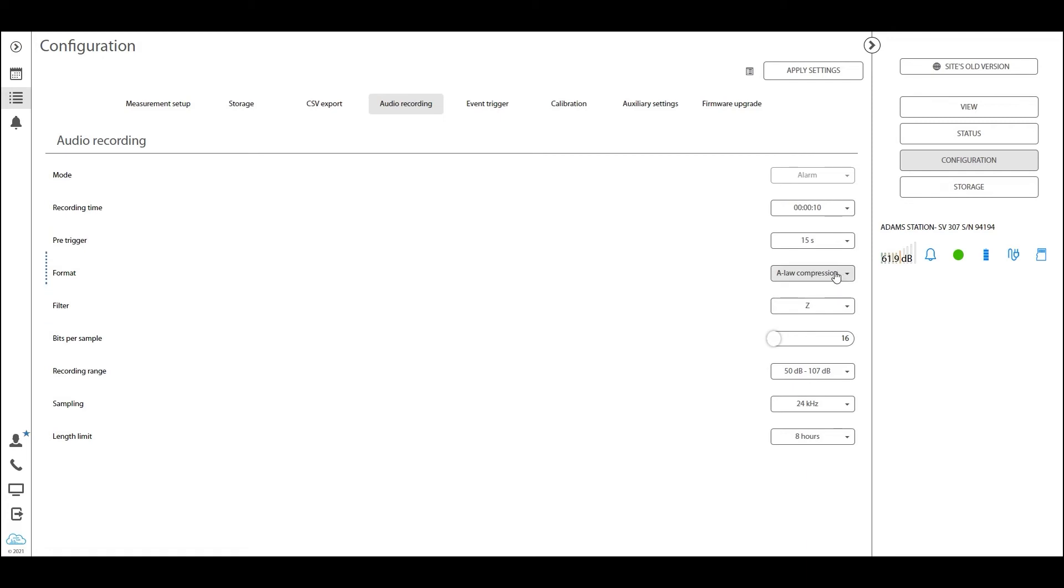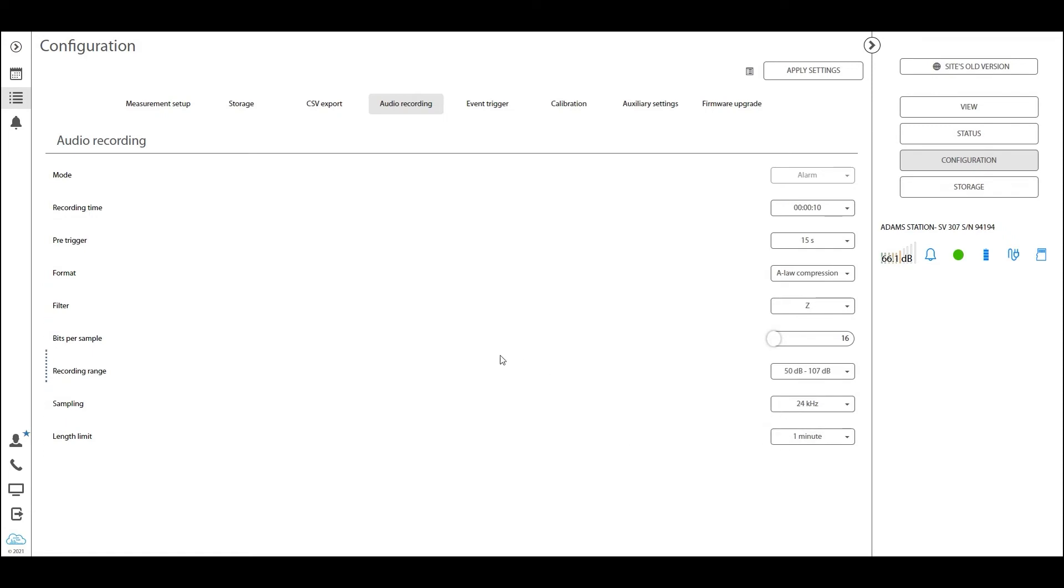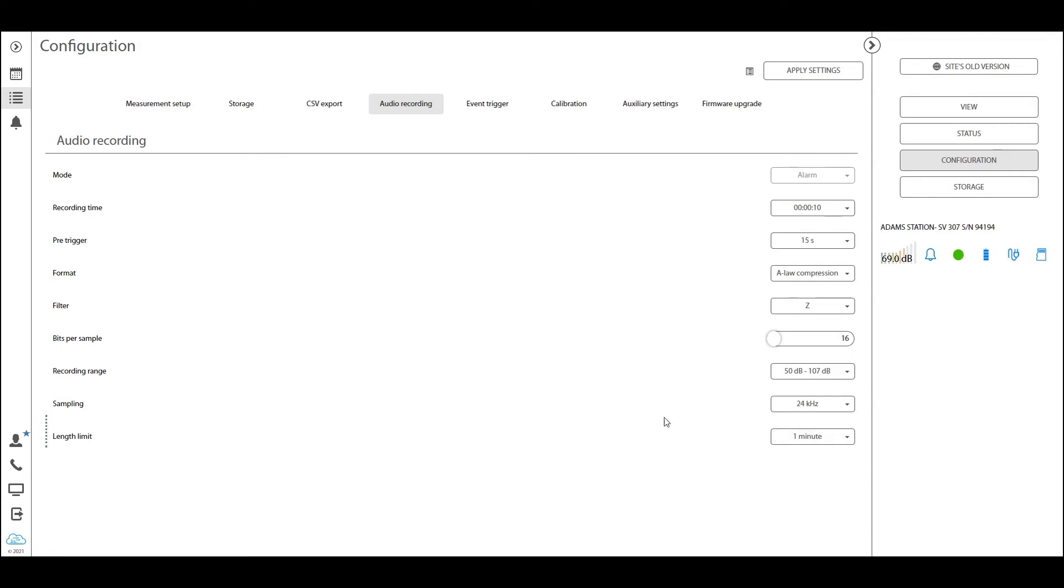A-law compression means that we will be compressing the file and it will have 8 bits per sample. And the length limit means how long this measurement and how long this audio file can be. I recommend it to set to a shorter period. Now if we have a situation where the 85 dB threshold is being breached for a very long time and the audio recording keeps on going, this length limit will result in that wave file or that audio file being split. So you will not end up with a huge two-gigabyte long or big audio recording. You will have a bunch of small one-minute audio recordings. Now you set it up in any way you want. Perhaps you want to have the full bits per sample, then you can set that up here. Then you don't have to choose the recording range.